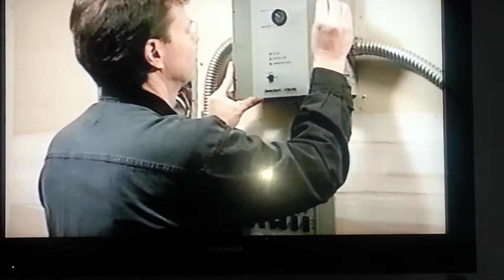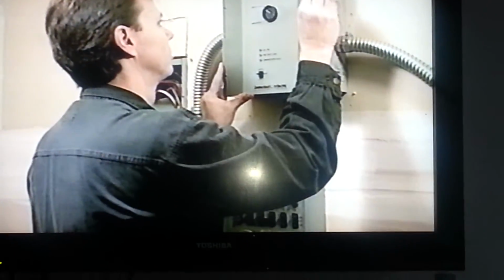When you have finished connecting the engine control to the generator, connect the control cable to the modular jack located in the lower left corner of the engine control circuit board. Connect the other end of the control cable to the jack labeled Control on the ATS transfer switch front panel. Double-check all your wiring connections and replace the cover of the ATS transfer switch.